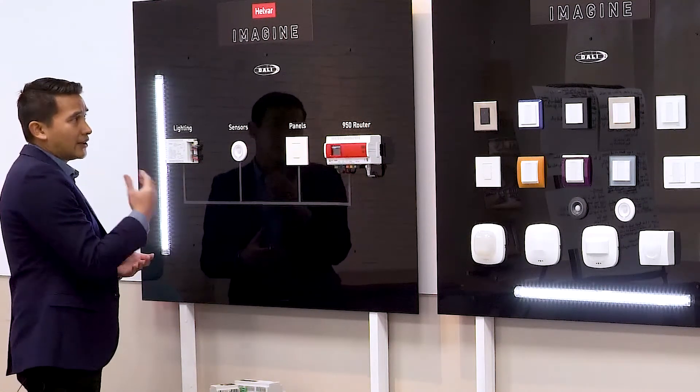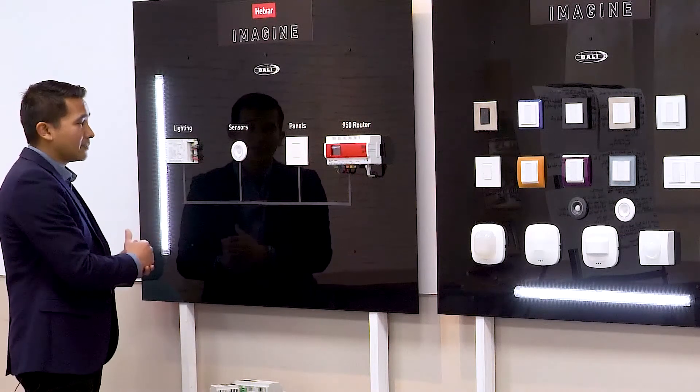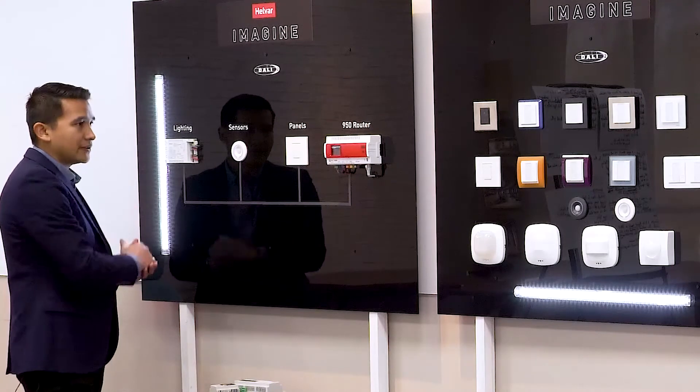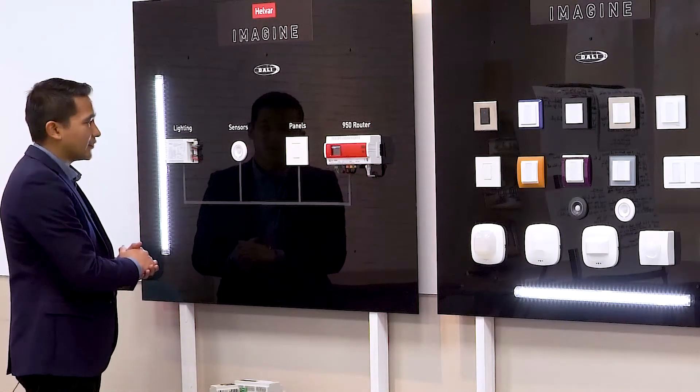Secondly, DALI 2 adds some more features on top of original DALI. For example, it standardizes the data available from the LED drivers, such as energy and burn hours, now available in a standardized format.